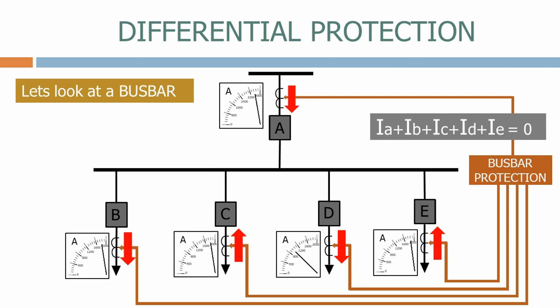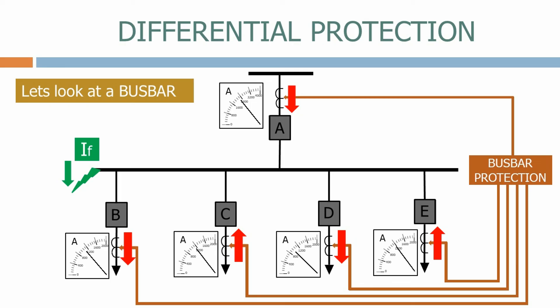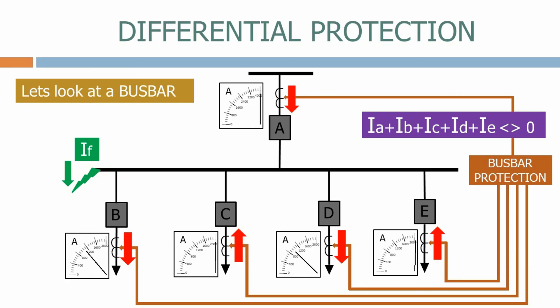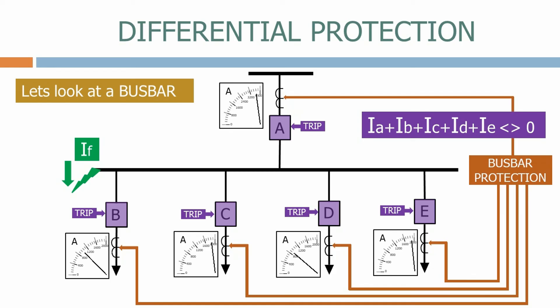Let's now apply a fault on the busbar. The current magnitudes will increase on the incomer and all feeders able to back-feed the fault, but this time, because some current is leaking out of the system, the sum of the currents on the incomers and feeders connected to the busbar no longer equals zero. The busbar protection system operates, tripping all of the circuit breakers connected to the busbar and clearing the fault from the rest of the system.